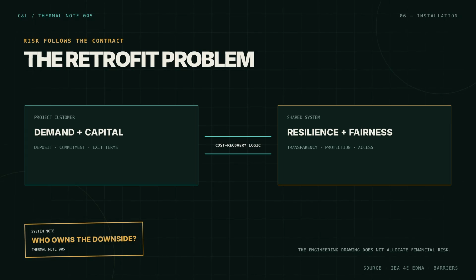The fastest growing opportunity may also be the hardest. Existing multi-story data centers were designed around air, floor loading, and pipe routes that may not fit new liquid systems. Retrofitting can require shutdowns, structural checks, new water loops, and coordination across server and facility vendors. The EDNA report highlights high initial cost, limited standardization, long-term reliability concerns, and the need for better retrofit solutions. This creates value for integrators and service companies that can manage interfaces. It also creates risk. A component may be technically excellent but difficult to qualify inside a customer's operating environment.